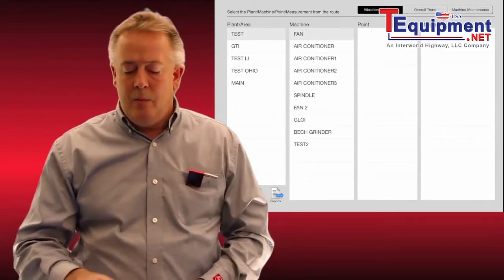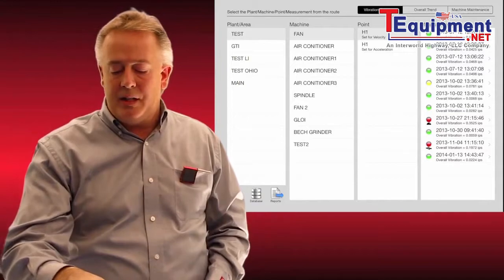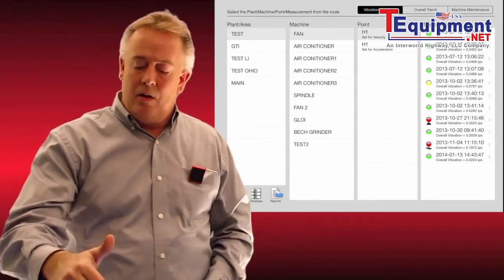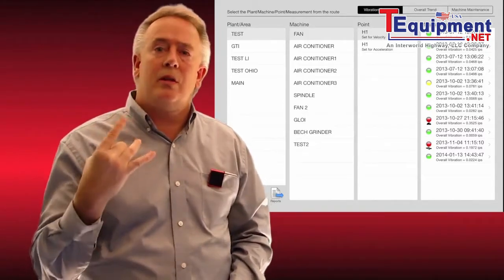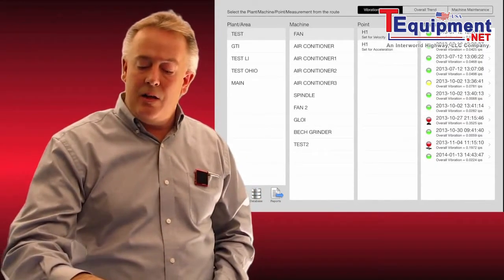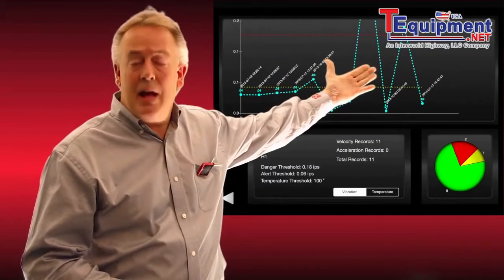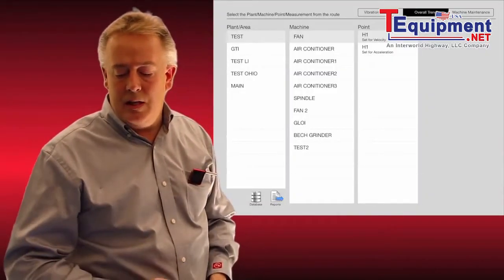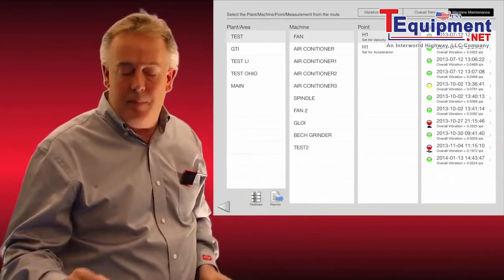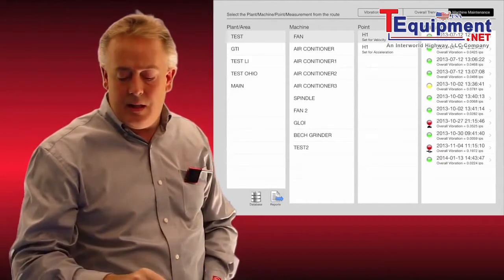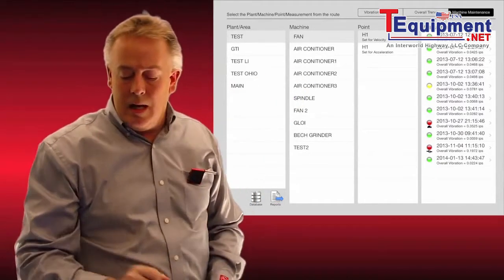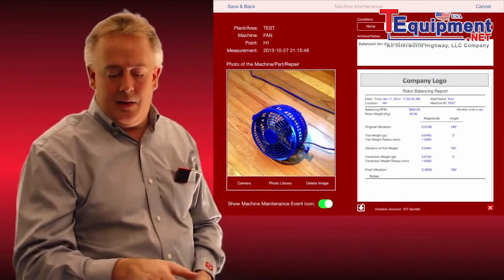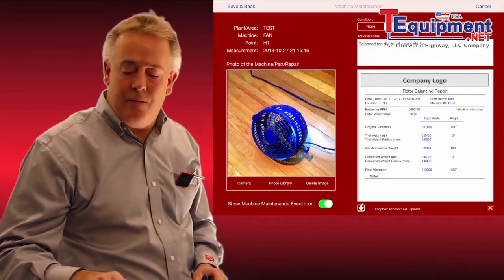Let's go into the iPad viewer. We'll go to that same test point, that same fan, and the H1 position. You can see a nice list of all the different readings I've taken from 2013 all the way through to today. Those points are in green, yellow, or red, indicating where I stand at that asset point against the alert thresholds. Hitting the overall trend shows a beautiful trend of that data point with all the dates. On the machine maintenance view, a couple of red readings have maintenance events — a balancing icon or alignment icon — and clicking on one shows that full maintenance event with a picture of the fan, notes, and the complete balancing report.